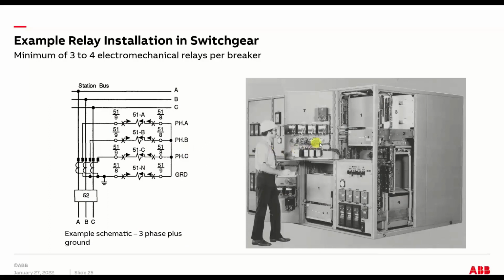Here's an example of what I was talking about before, where you have multiple relays required for the protection of a single circuit breaker. This was pretty typical. This is old GE gear, I think Power Break. So these are probably GE relays too, circa 1980 probably. But you can see here's a three-line diagram. You can see this one breaker, and this is pretty much the most basic overcurrent protection you can put on it, with three relays for phase overcurrent and one relay for ground overcurrent. So four relays in total with all the associated wiring just for one breaker.